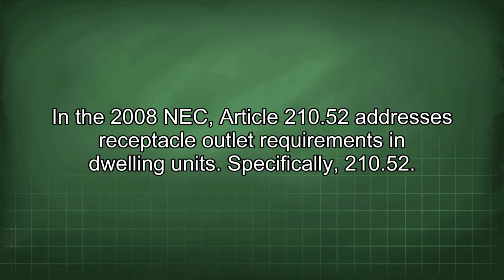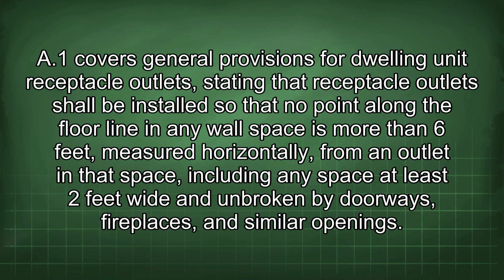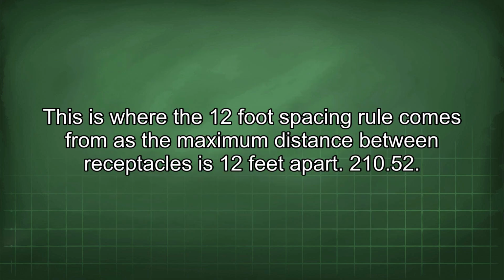Specifically, 210.52(A)(1) covers general provisions for dwelling unit receptacle outlets, stating that receptacle outlets shall be installed so that no point along the floor line in any wall space is more than 6 feet, measured horizontally, from an outlet in that space, including any space at least 2 feet wide and unbroken by doorways, fireplaces, and similar openings. This is where the 12-foot spacing rule comes from, as the maximum distance between receptacles is 12 feet apart.